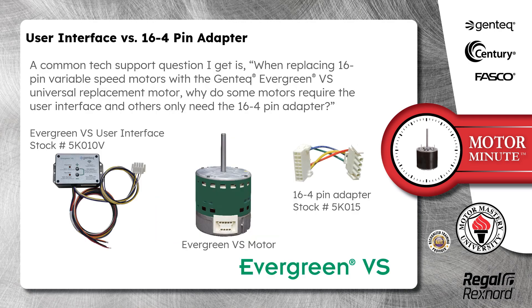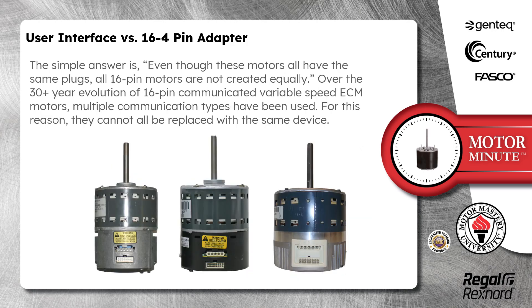A common tech support question I get is: when replacing 16-pin variable speed motors with the Genteq Evergreen VS Universal Replacement Motor, why do some motors require the user interface and others only need the 16-4-pin adapter? The simple answer is, even though these motors all have the same plugs, all 16-pin motors are not created equally.